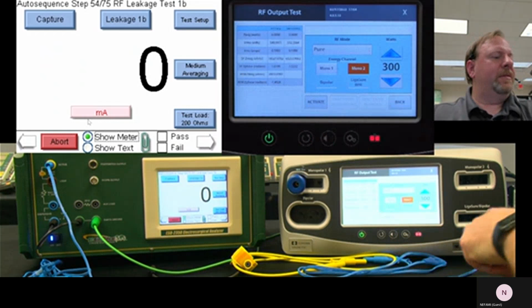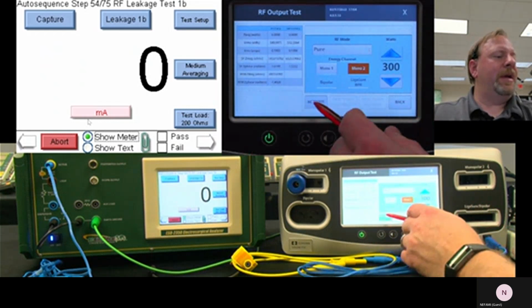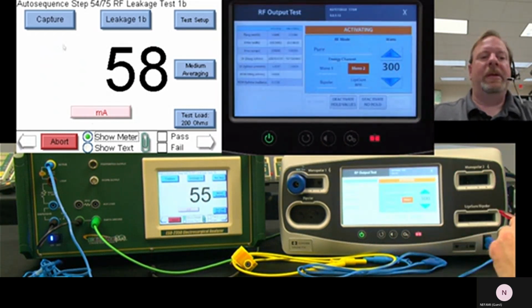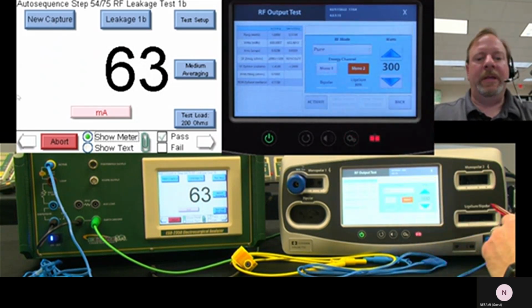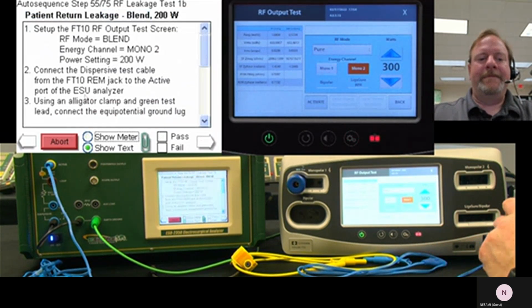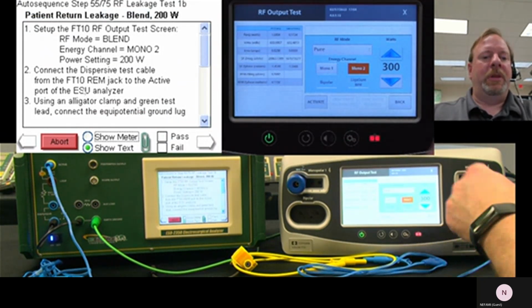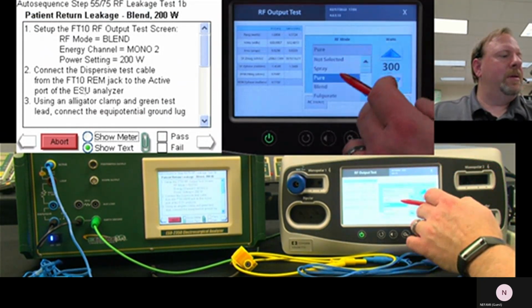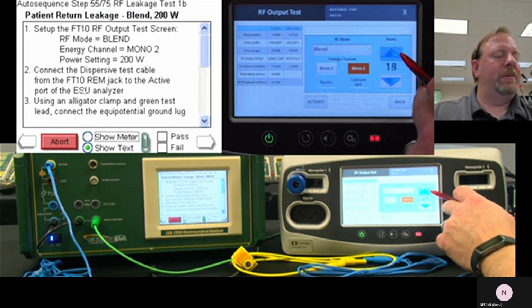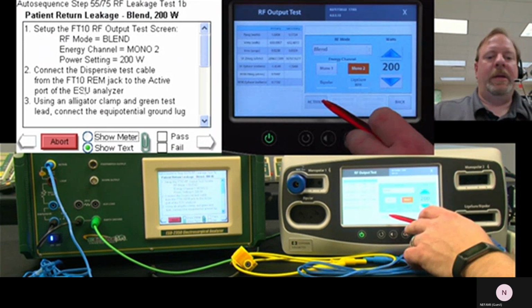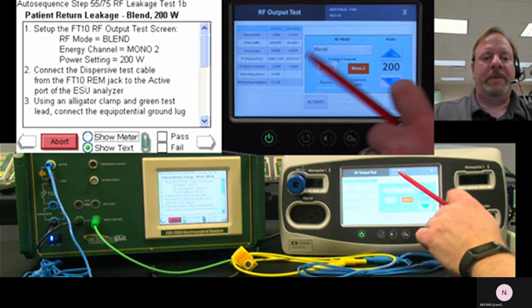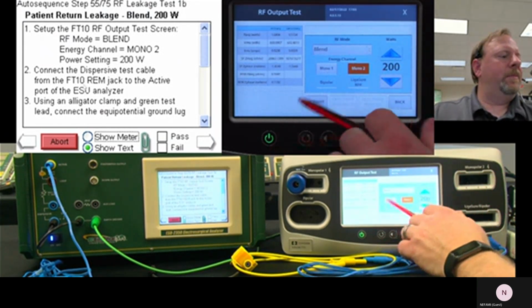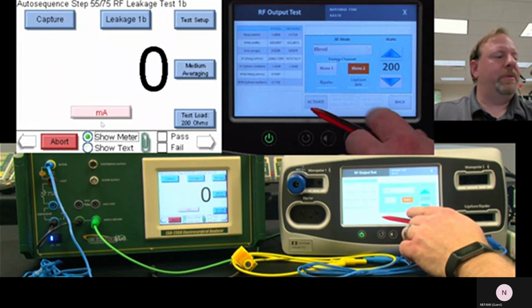And 300 watts, monopolar 2, activate. Yes. And there's our reading. That is our REM leakage to ground. Okay, then we go to blend, max power, both settings. And dispersive. Yep. Show meter.